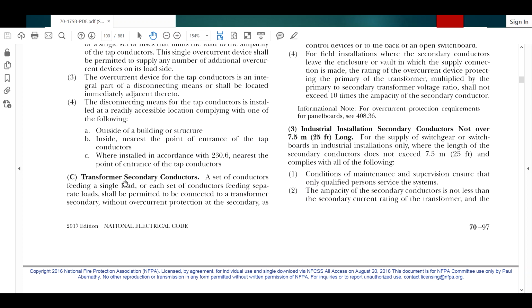Well, before we do anything, let's read C, because here we're dealing with secondary conductors. Number 1, it says a set of conductors feeding a single load, okay, and that would be like feeding our panel that we just looked at. It says, or a set of conductors feeding separate loads, so I could have multiple panels being fed from a single transformer. That's okay, as long as that transformer is sized properly to handle whatever the load, the secondary current can actually handle it. Okay, it says, shall be permitted to be connected to a transformer secondary without overcurrent protection at the secondary.